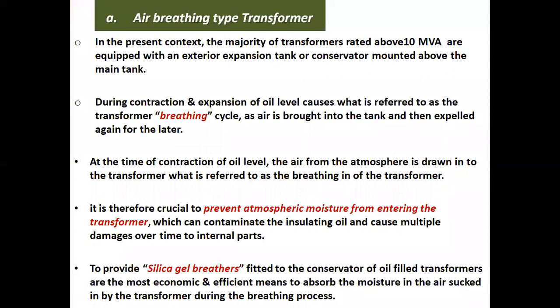Let's start with the air breathing type transformer. In the present context, the majority of transformers rated above 10 MVA are equipped with an exterior expansion tank or conservator mounted above the main tank. The contraction and expansion of the oil level causes what is referred to as the transformer breathing cycle, as air is brought into the tank and then expelled again.